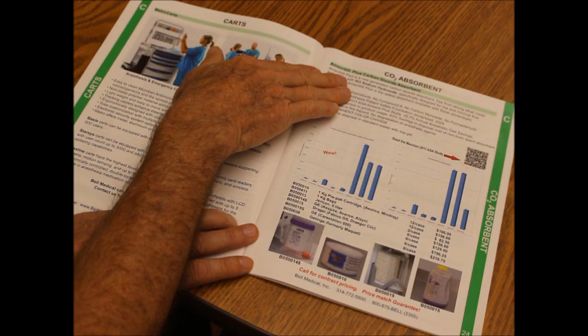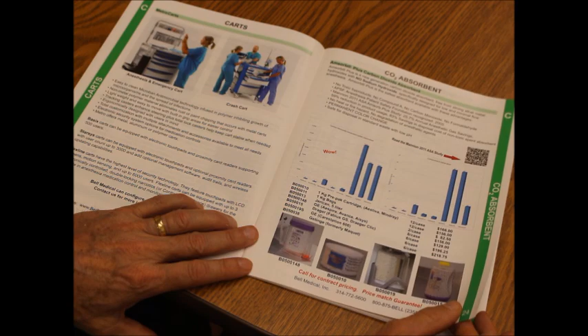It's a safer absorbent to use, allows you to do lower fresh gas flows that end up reducing the amount of anesthetic agent that you use, and thus reducing your OR's carbon footprint because less agent escapes to the atmosphere. It also has a lower pH, so it's safe for our landfills, whereas other CO2 absorbents have a high pH and they're caustic and should not be put in landfills, and they should be red bagged. Amsorb Plus, along with our other absorbents that we stock, contain no sodium hydroxide.